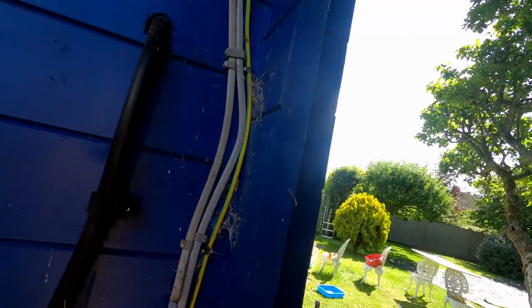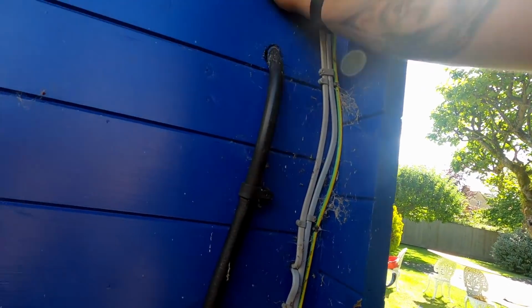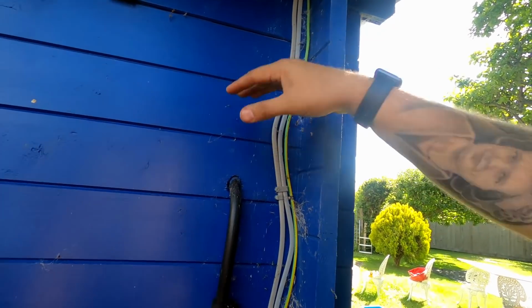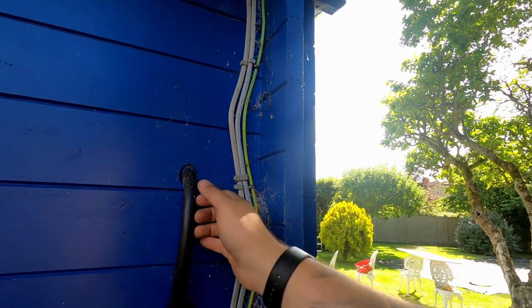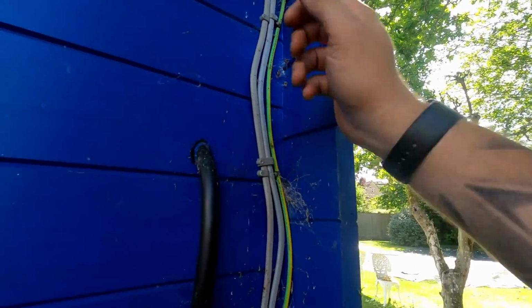After doing a little bit of checks and whatnot, we've got a Ze at the pool house of 5 ohms. What they've done, it's a 10mm armoured - it's been here since before the shed was built, there was already a smaller one here. Anyway, they've used the steel as the CPC, and it's a 10mm cable, so that actually needs to be the equivalent of 80mm in order to provide satisfactory function as a CPC.